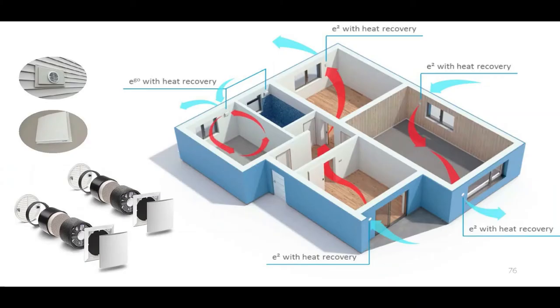You don't have to have a fully ducted system to achieve balanced ventilation. Lunos and Vents US are two examples of through-the-wall ductless heat recovery ventilators. Evaluation of these units should include airflow rating, sound transmission, and room diffusion for occupant comfort. A power source must be supplied to each device, and each device must connect to a controller. We've measured poor air quality in rooms where the Lunos system is split with only one port in a room and a door separating the room from another location with the other port. That was shown in the prior case study. Even with the constant switching from supply to exhaust, CO2 levels were elevated when the door was closed.